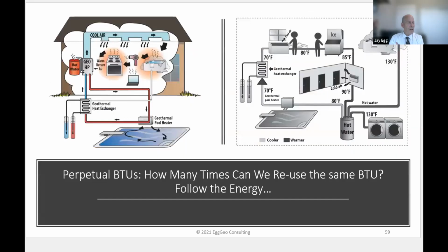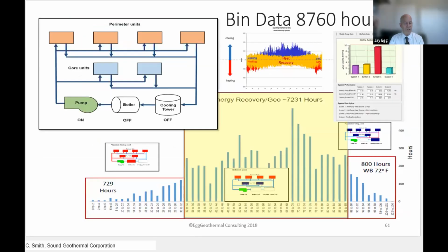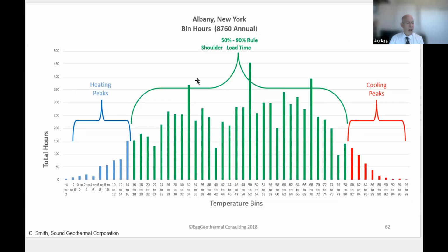So that's easy to understand when you consider that normally in a building, all of the heat producing appliances, whether it's bathing, cooking, blow dryers, computer equipment, is all being taken into the air conditioning equipment and normally rejected outside. All that heat can be put into hot water systems, pools, and it can go beyond that when you look at a resort or a campus type application. That can go to cooking equipment, laundry equipment, kitchen equipment, common area equipment. And as you chase the BTUs around a building, you see that the BTUs begin to be reshared between heating and cooling appliances. So that's what these images are all about, showing that potential, as in Albany, New York here, a potential for energy sharing most of the year.